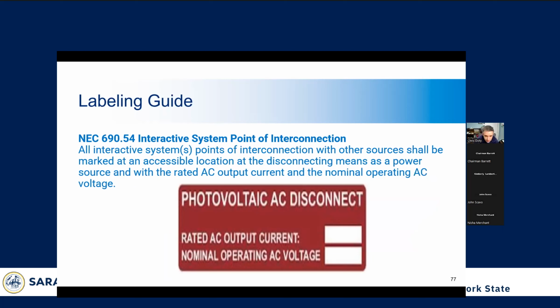Moving on, here we have the PV AC disconnect label. So anytime you have an inverter output, that's what's known as an interactive system point of interconnection, and you have to provide this label with the rated AC output current and the nominal operating voltage. So something to keep in mind is NYSERDA does not allow writing in on these labels. They want it to be engraved or printed.